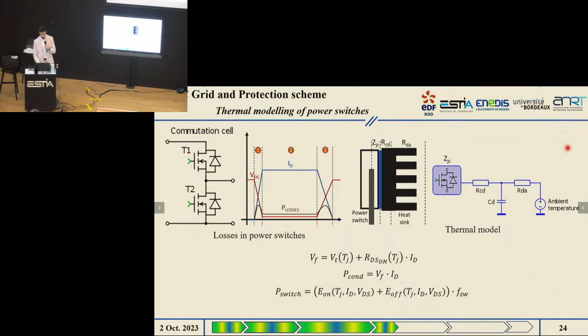And in terms of temperature evolution, in a power electronics converter, it is mainly due to two types of losses, which are conduction losses that you can see here, and in 1 and 3 you can see the commutation or switching losses. These could then be modeled as a heat flow passing through a set of impedances: the impedance from the junction of the semiconductor to its case, the impedance between case and heatsink, and finally the impedance between heatsink and the air. And this set of impedances and heat flow generated by losses can be modeled in the Plexim platform, as you can see here in the picture.